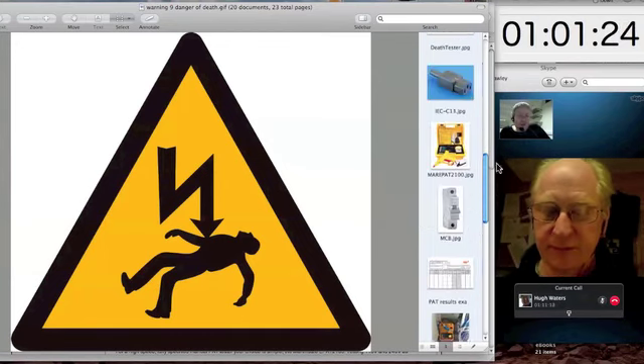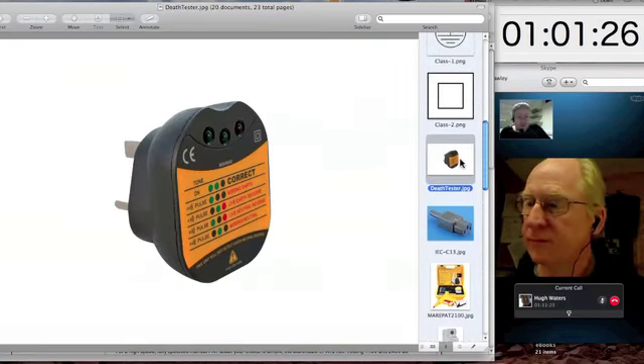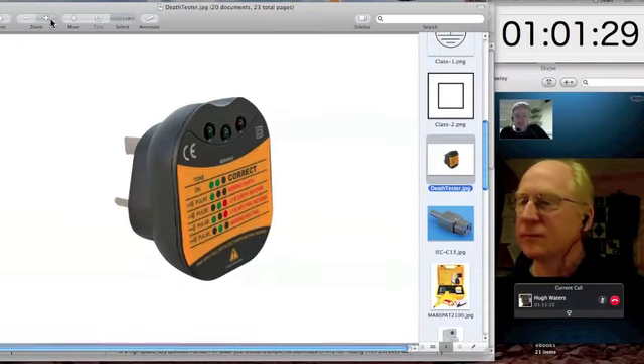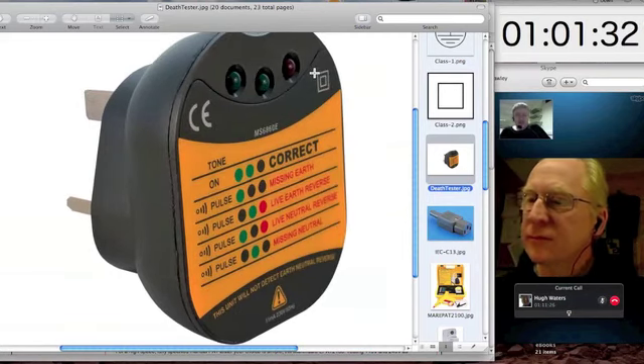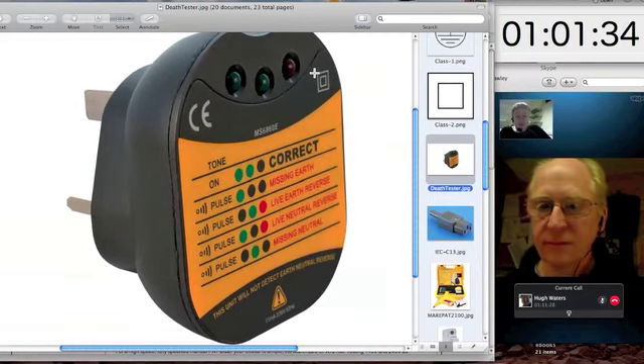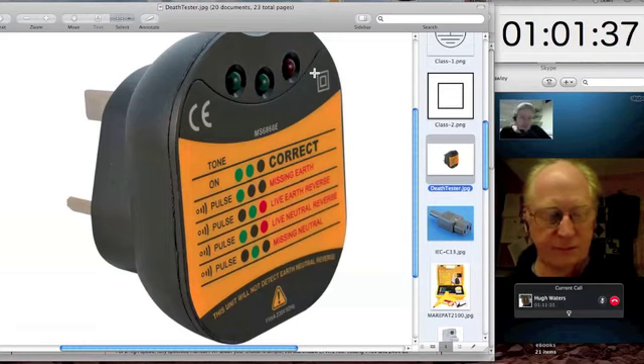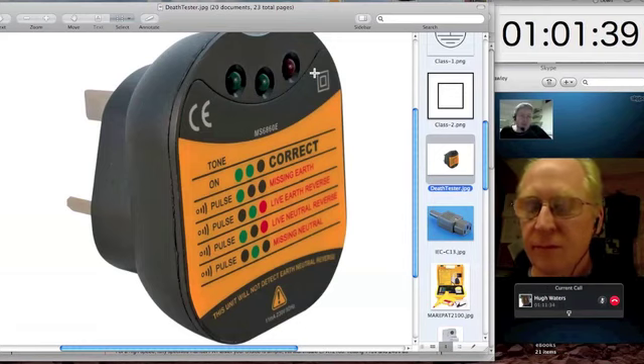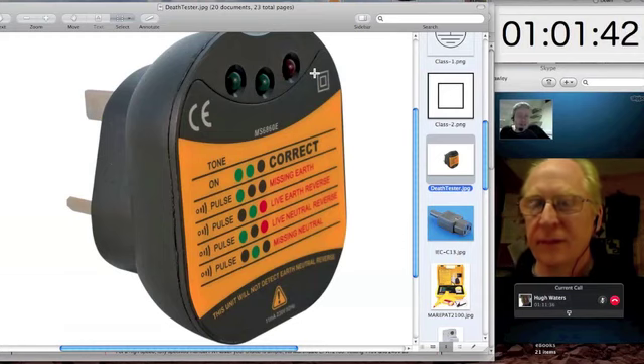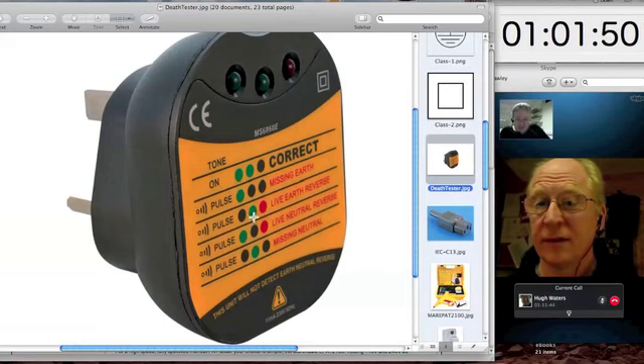Very nasty. One of the things that I keep in my rucksack the whole time is one of these little death testers, and they're fantastic little gadgets, 15 quid or whatever, and what it does is it measures the potential difference between live and neutral, live and earth, and neutral and earth, and that very quickly tells you if you've got a functioning earth, if you've got volts between live and neutral, and they're the right way round. And rather splendidly, some of these more modern ones beep as well when things are correct. So you can literally go along a supply, bang, bang, bang, bang, and so long as you're hearing the beep, you know that you're well in the ballpark of things being wired correctly.